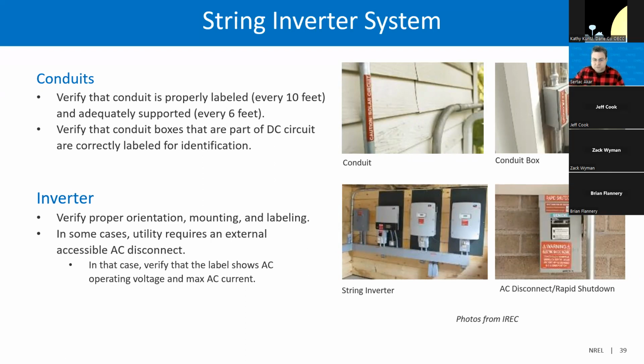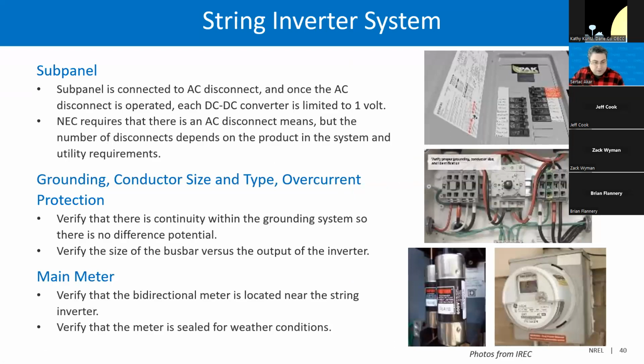In some cases, the utility requires an external accessible AC disconnect. In that case, the inspector must verify that the label shows AC operating voltage and maximum AC current. The sub-panel of the string inverter system is connected to the AC disconnect, and once the AC disconnect is operated, each DC-DC converter is limited to 1 volt.